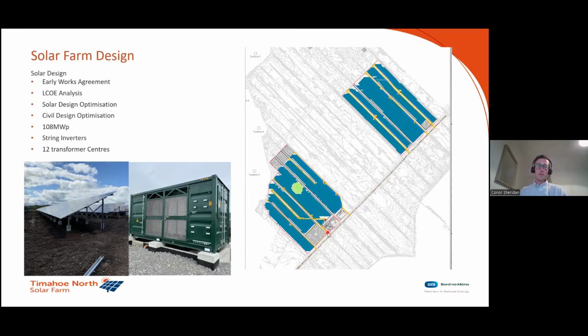That was the civil side. Here's the final layout of the two arrays, north and south, a 108 megawatt peak design. We've got string inverters, so the power created at the module goes back to a string inverter, is converted from DC back to AC, and then goes to transformer centers. There were 12 transformer centers on site, and the voltage is stepped up from 800 volts to 33 kV. From the transformer center, shown here in the green container, it goes via an underground cable to the substation, where at the grid transformer it's stepped up again to 110 kV, and then exported to the grid.